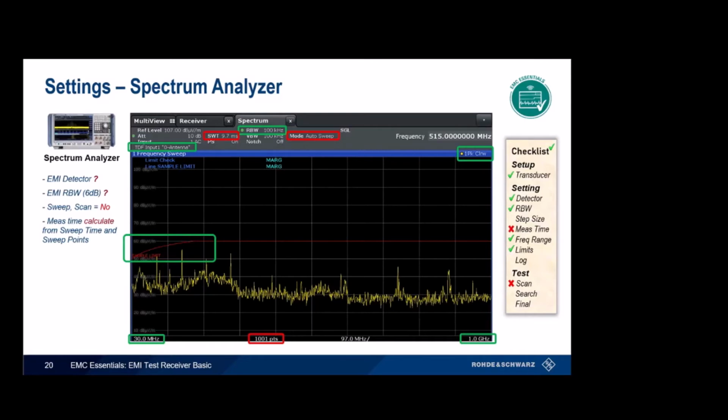On a similar note, I know the frequency range and the sweep points, so I can calculate the step size between frequency points. Again though, adding the calculation comment to the notes, but mark failed in the checklist.